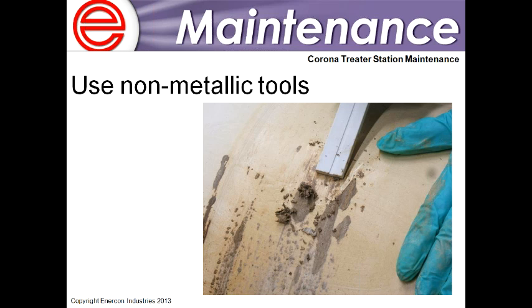And then here's a picture of use only non-metallic tools. In this case, that's a ceramic bar, another ceramic strip, being used to scrape off that heavy debris. But never, ever use any files or metallic items, because that can leave little shards of metal in the ceramic, which is going to lead to localized heating and shorten the life of the ground roll.